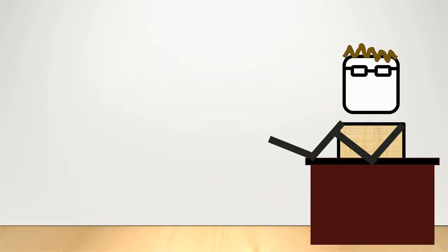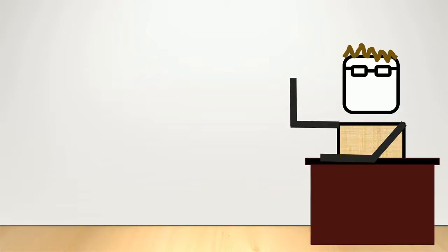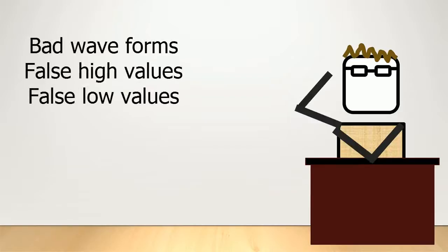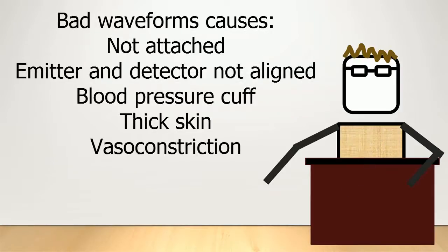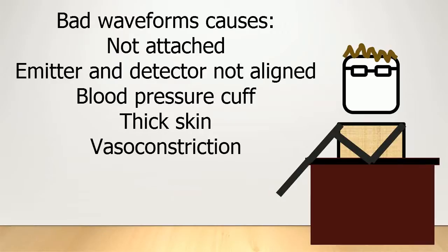If you've ever used a pulse oximeter, you know by now that there are problems with the measurement or with the device. The problems you encounter are frequently bad waveforms, and also you can run into problems with false highs and false low numbers. One of the most frequent issues is a bad waveform.